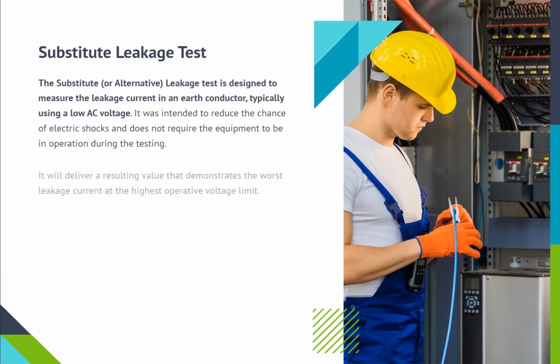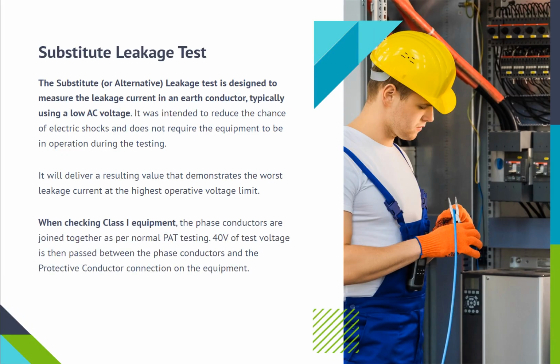Substitute leakage test. The substitute, or alternative, leakage test is designed to measure the leakage current in an earth conductor, typically using a low AC voltage. It was intended to reduce the chance of electric shocks, and does not require the equipment to be in operation during the testing. It will deliver a resulting value that demonstrates the worst leakage current at the highest operative voltage limit. When checking Class I equipment, the phase conductors are joined together, as per normal PAT testing. 40 volts of test voltage is then passed between the phase conductors and the protective conductor connection on the equipment.